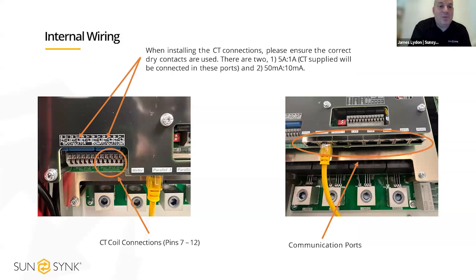Okay, so on the left-hand side, we've got our terminal strip. This is for your CT coils. If you are using the CT coils that are in the box as standard, you would use the terminal strip to connect them to. You'd have two cables essentially if it's single phase, and with the 3-phase, it'll be 6. But if you are using the digital Eastron meter, just to the right of the image on the left, you've got the meter input. That will be the connection from the Eastron meter connected into us on that patch lead.